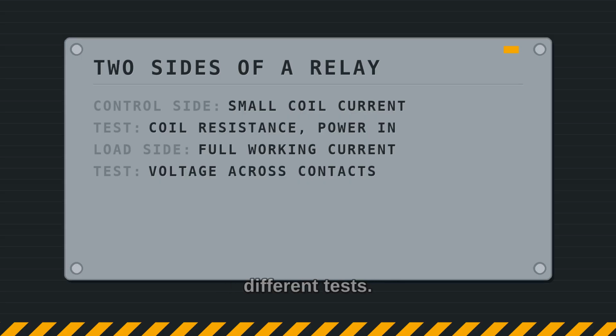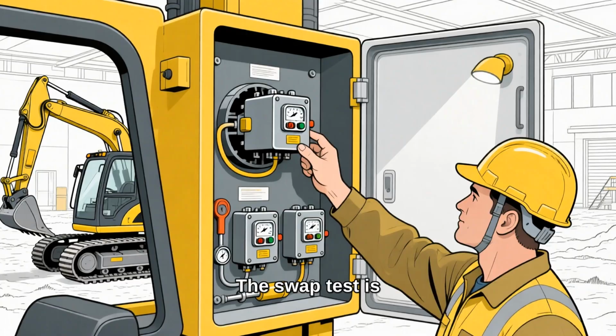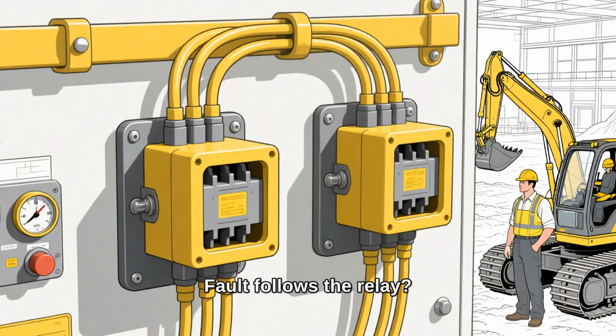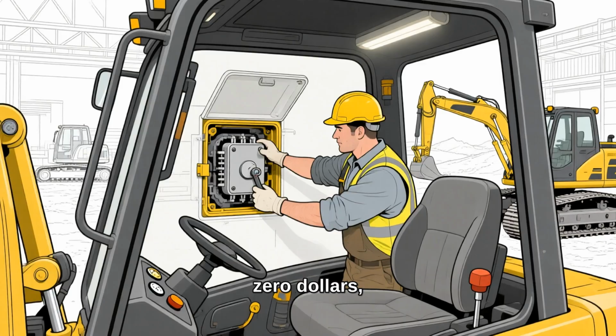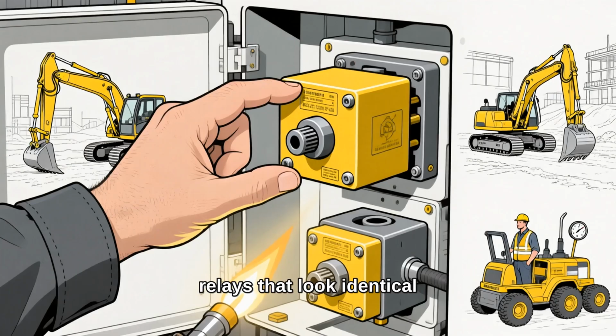Different failures, different tests. The swap test is free. Find an identical relay running something you don't need right now and trade them. Fault follows the relay? It's the relay. Fault stays put, you just proved the relay innocent for nothing. That's 5 minutes and $0, and it clears the part everybody guesses first. One catch: relays that look identical aren't always identical inside. Check the part numbers before you trust the result.